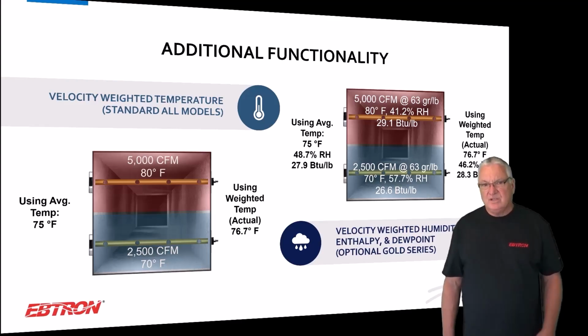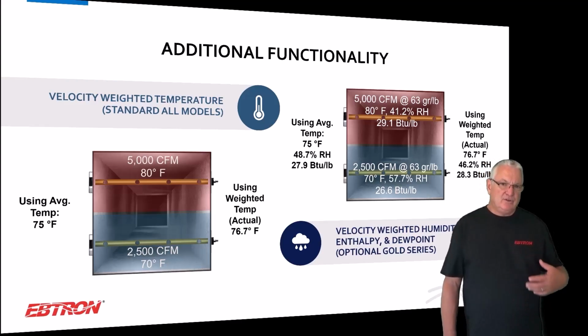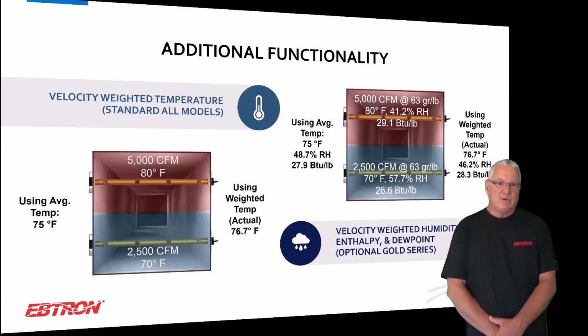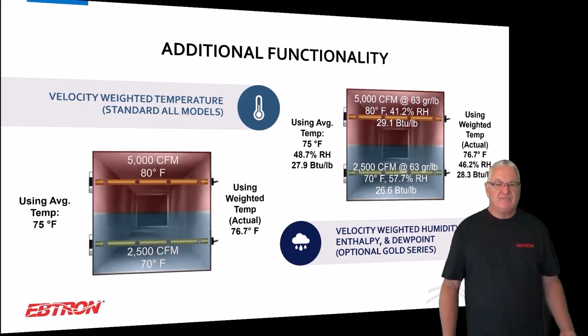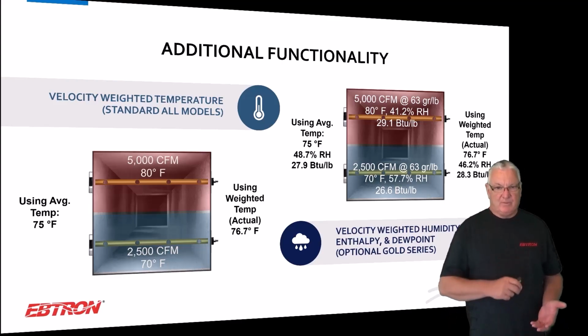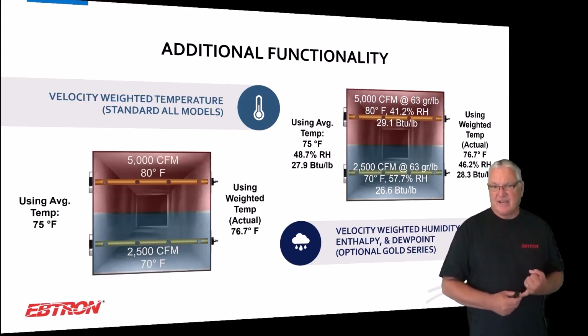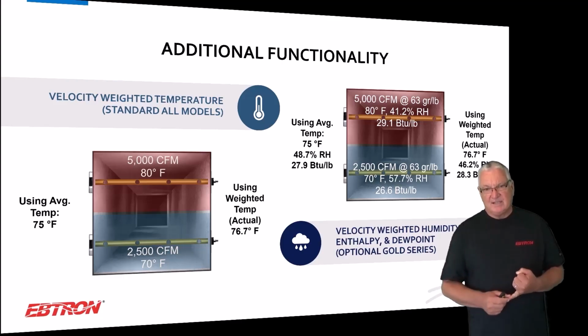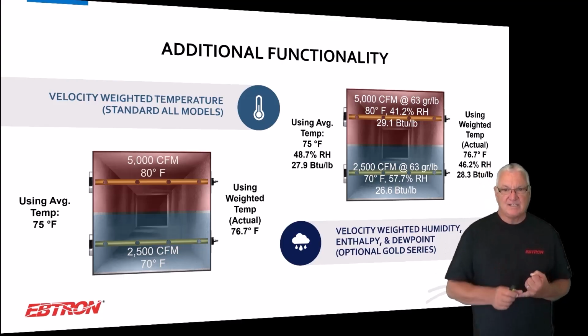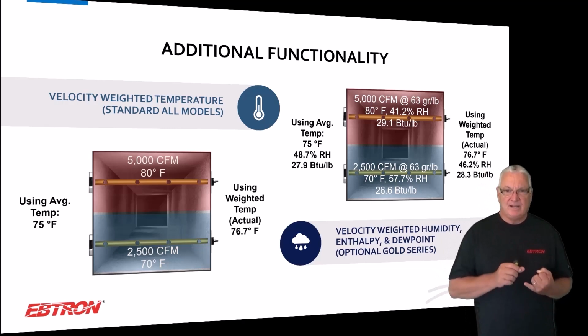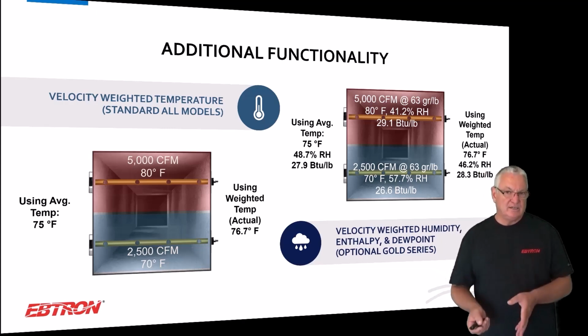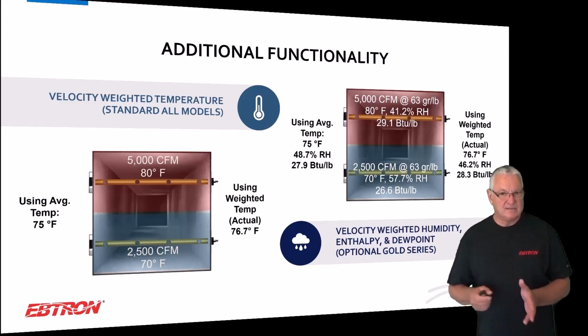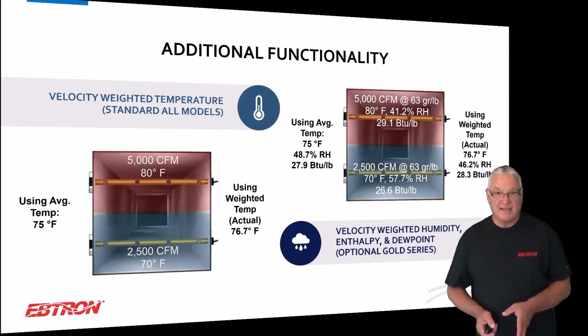And so this is something I think people should look into more, use more when they're putting flow meters in outside air. Of course, there's plenty of other applications where you want to know these different things. We basically provide you with a velocity weighted temperature standard, velocity weighted humidity. Once we add this humidity sensor, you can get velocity weighted humidity, velocity weighted enthalpy, or dew point. Now that's only on our Gold Series product right now, but that's most of what our business is anyhow.